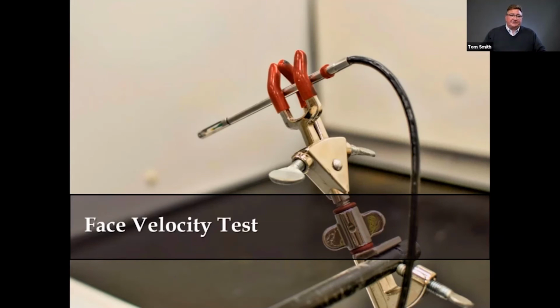So our next test that we're looking at is the face velocity test. We want to evaluate how well the airflow is moving through the face of the hood and its uniformity from top to bottom, left and right. And we want to evaluate both the magnitude in terms of average velocity, but also the spatial variation and the temporal variation in terms of that velocity.